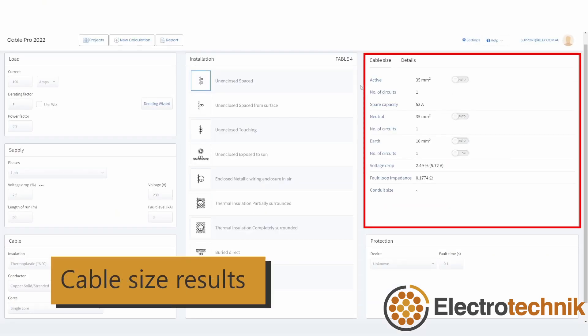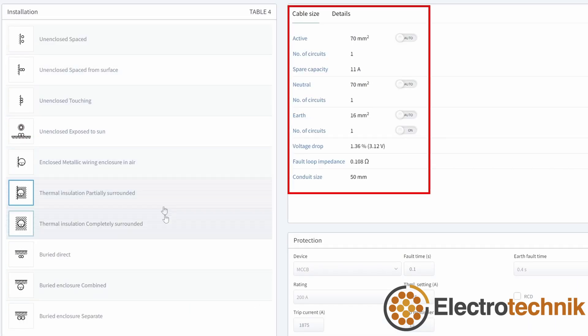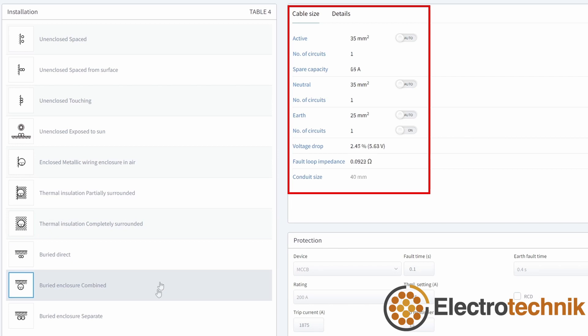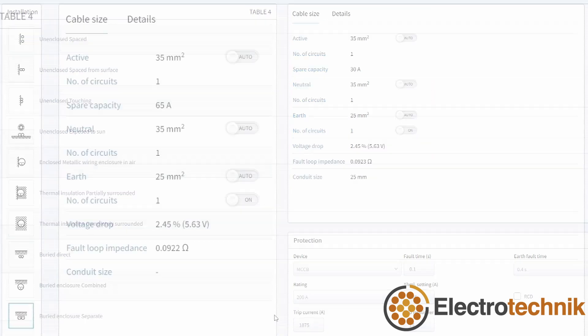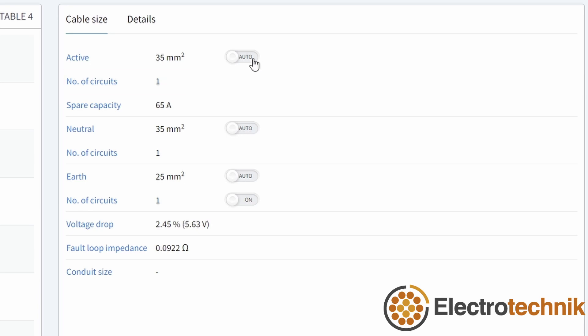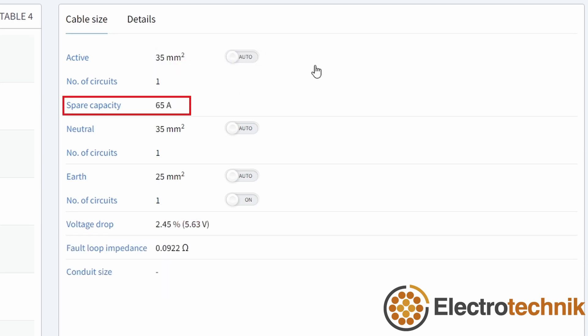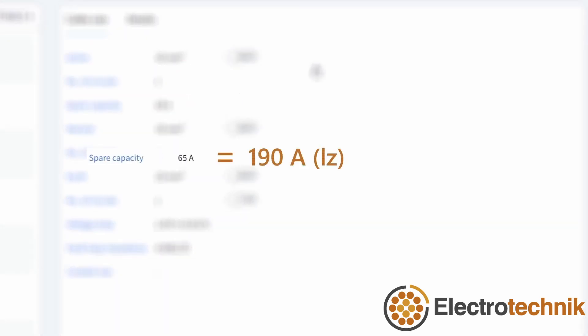Next, let's look at the cable size results. The cable size results are updated live with every change you make. The minimum active size is automatically calculated along with the number of circuits. The active size and the number of circuits can also be set manually and compliance will be checked. The spare capacity is the difference between the current carrying capacity of the circuits as per the standard and the protective device rating.